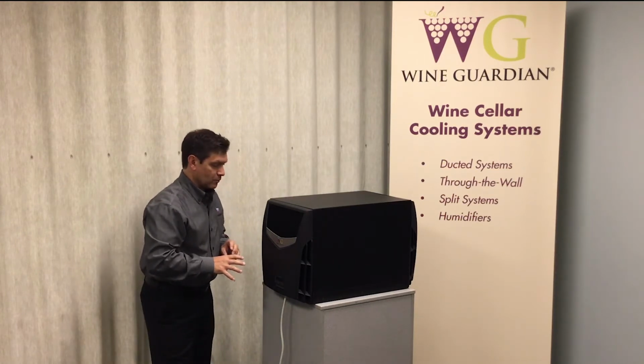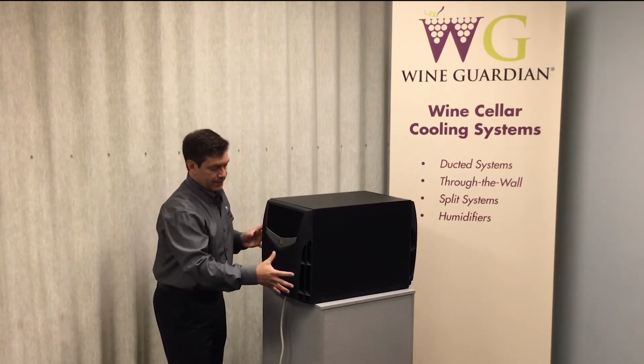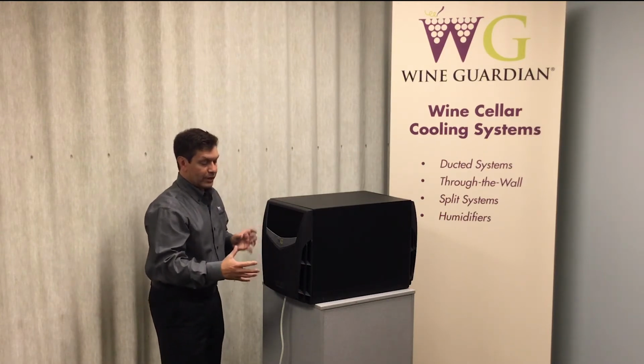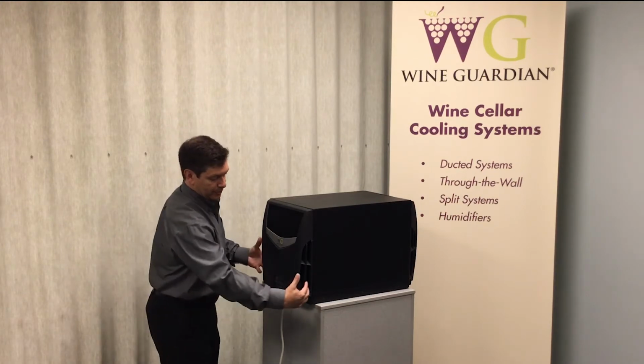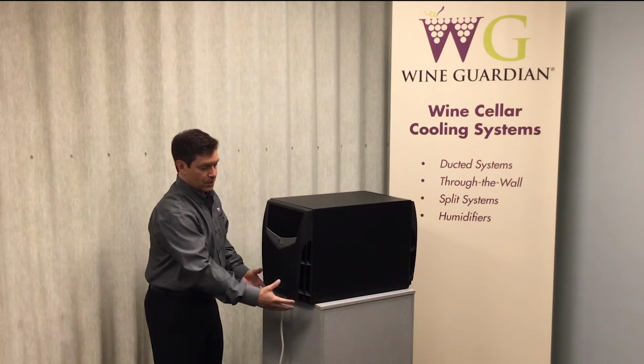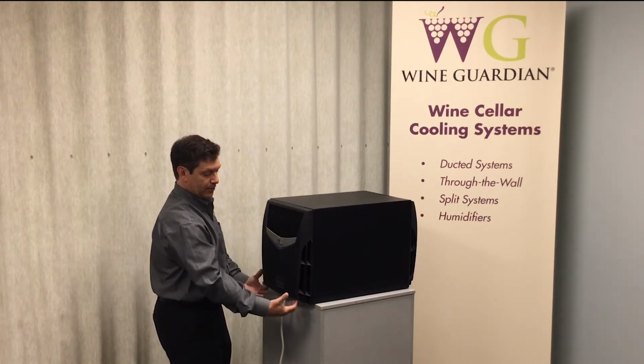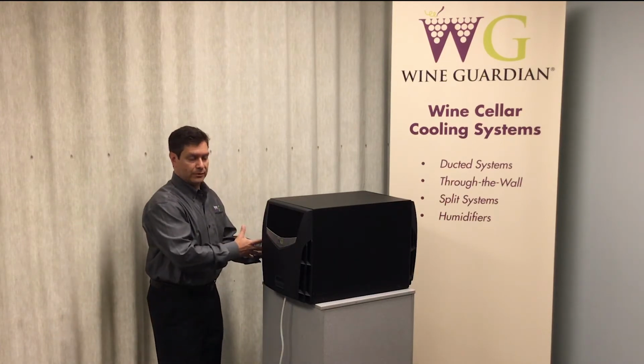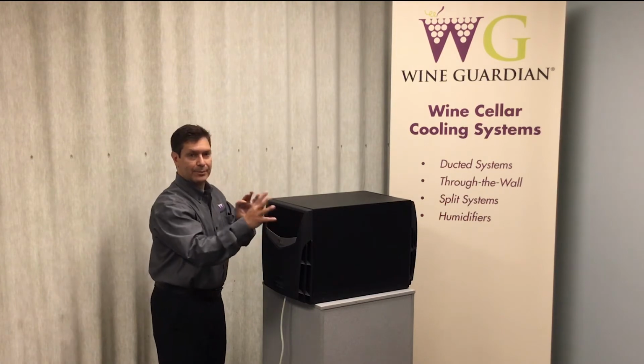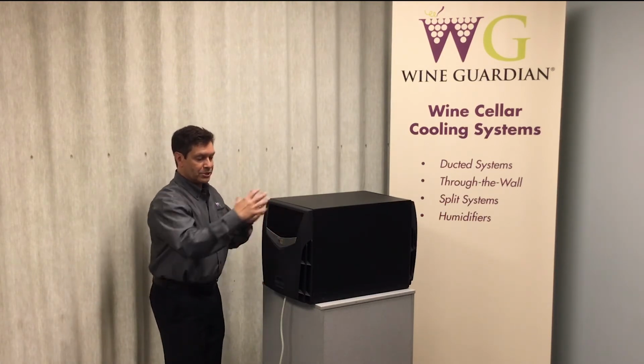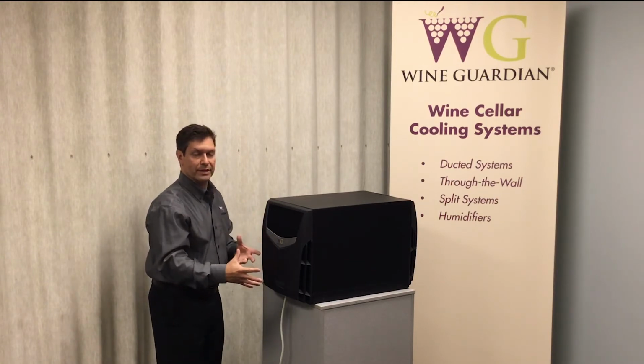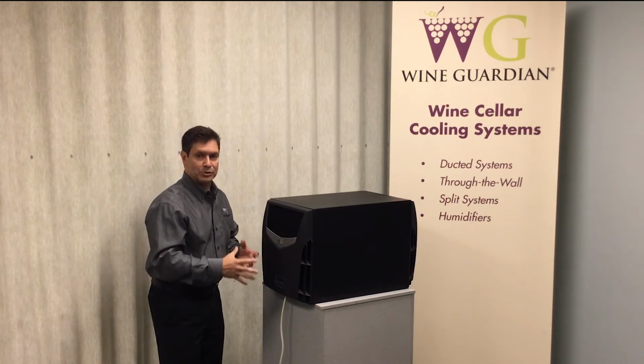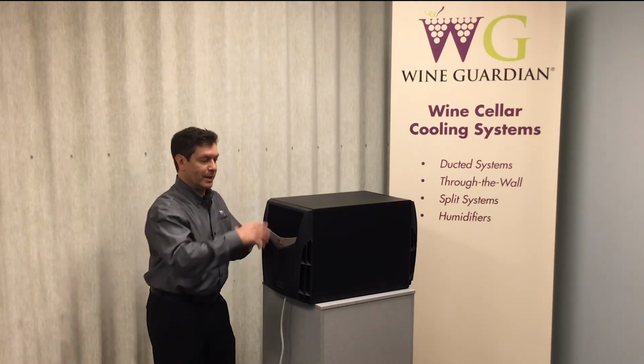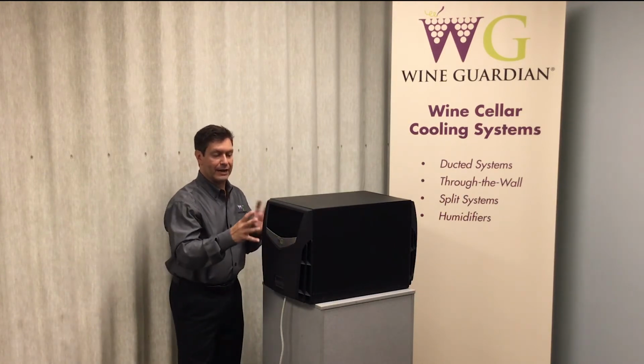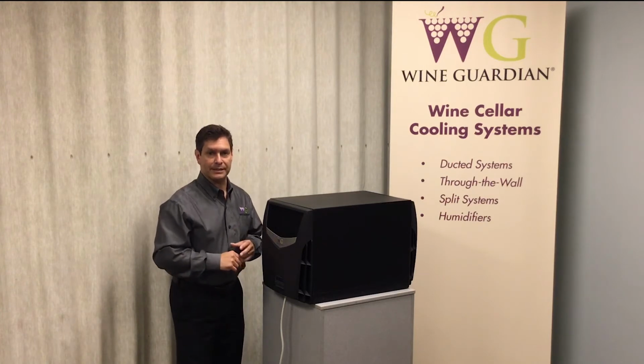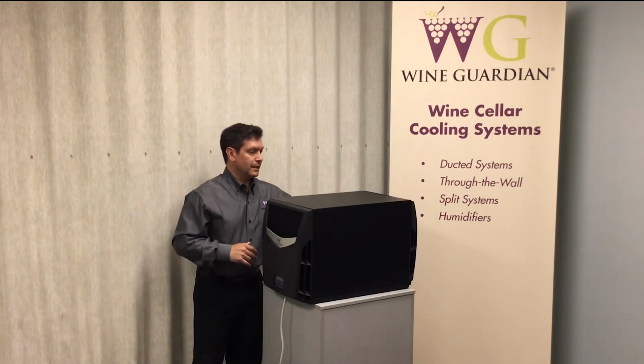The way that the system works once it's installed is the decorative grill here serves a purpose of bringing in air to the wine cellar cooling unit from the sides and the bottom of the unit. So return air from the wine room is coming into the unit from these areas, is drawn across the cooling coil, and then is blown out of this top section. So within your wine room, you want to make sure that this area is free. You want to give it enough room to breathe. It's not generally acceptable to put this in a corner of your space where it may be hitting another wall. You want to have it out in the open so that it can blow that cold air out into the space. Similarly, on the condenser side, the same holds true.